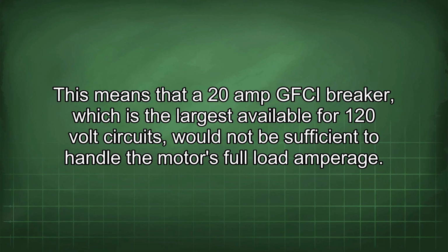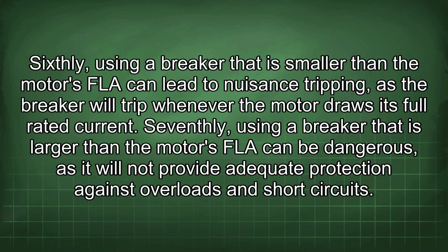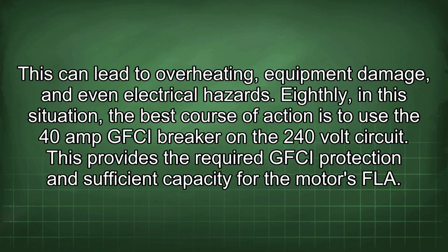This means that a 20 amp GFCI breaker, which is the largest available for 120 volt circuits, would not be sufficient to handle the motor's full load amperage. Sixthly, using a breaker that is smaller than the motor's FLA can lead to nuisance tripping, as the breaker will trip whenever the motor draws its full rated current. Seventhly, using a breaker that is larger than the motor's FLA can be dangerous, as it will not provide adequate protection against overloads and short circuits. This can lead to overheating, equipment damage, and even electrical hazards.